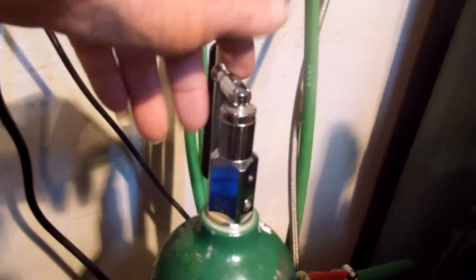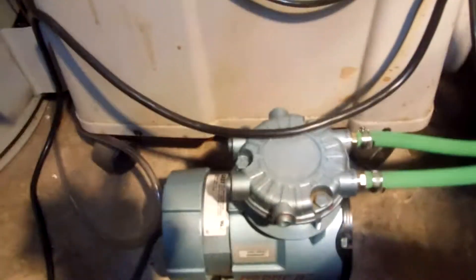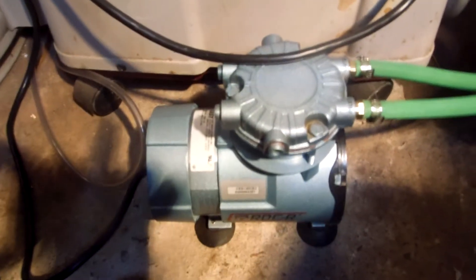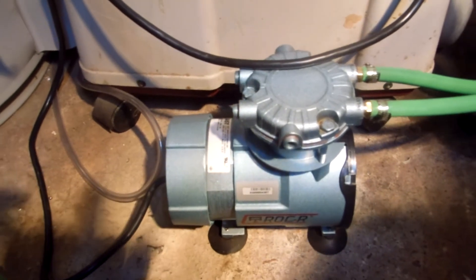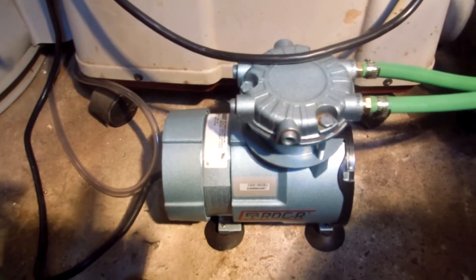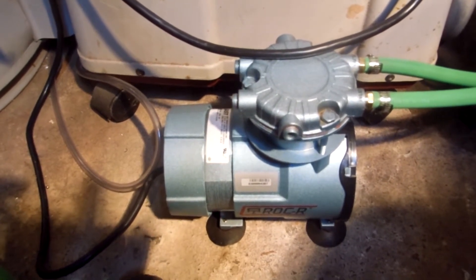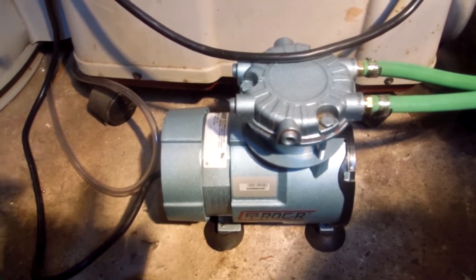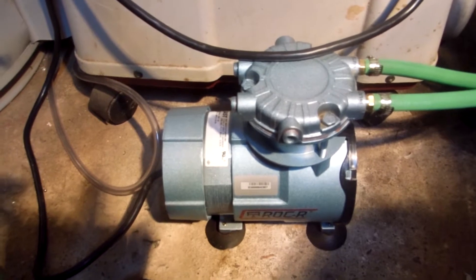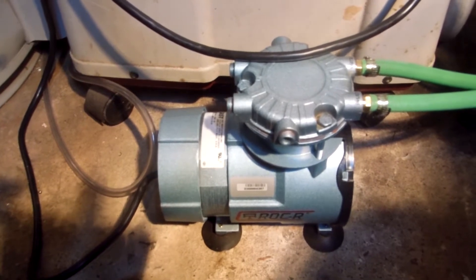Drain it with this valve right here for a little bit. So it's kind of like a blow off now, the pressure release for restarting the compressor.